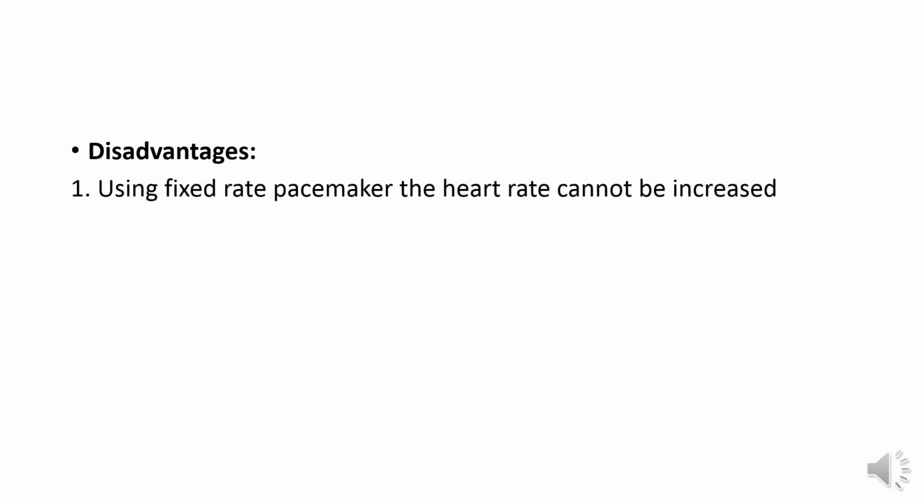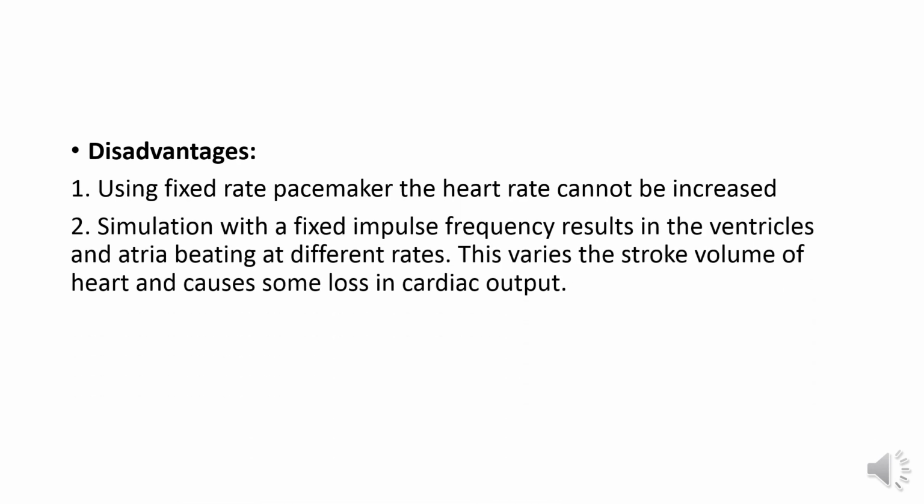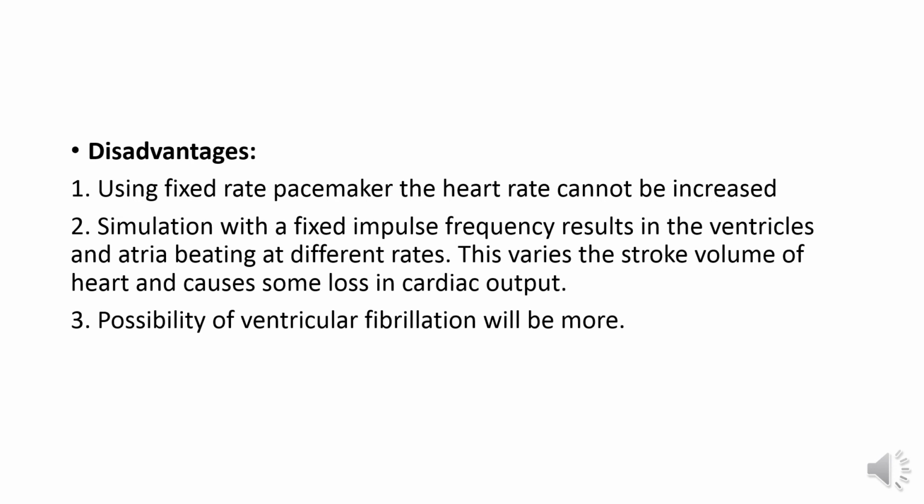There are some disadvantages of the fixed rate pacemaker. If you use the fixed rate pacemaker, the heart rate cannot be increased. Stimulation with a fixed impulse frequency results in the ventricles and atria beating at different rates. The varying stroke volume of the heart causes some loss in cardiac output. The possibility of ventricular fibrillation is higher.